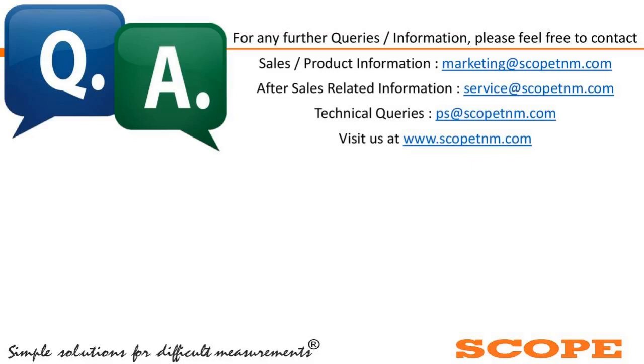Is it necessary to separate or disconnect the earth flat connection of the tower? No, sir, it is not recommended at all, because if at the time of measurement any surge or any fault comes into the system, then the earth strip is the only point of safety. And if we remove the earth flat connection, there could be a catastrophic failure, or a high voltage surge or step voltage effects. Anything can come. So from the viewpoint of operator safety and human safety, this earth connection to the tower, or for that matter for a normal earth resistance measurement, the strip of the transformer earthing or any such earthing strip, must not be removed, because then we are sacrificing our safety. So it must not be removed under any condition.